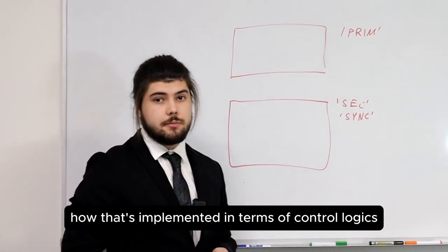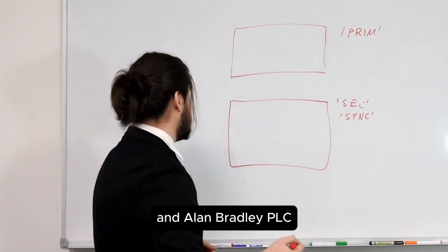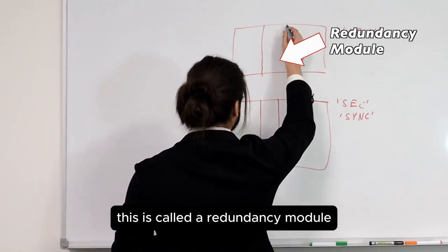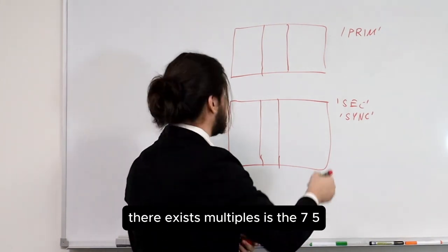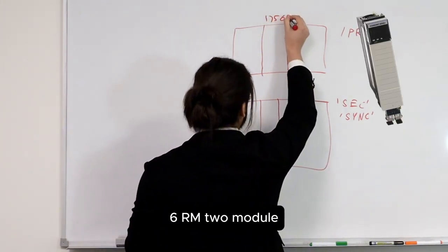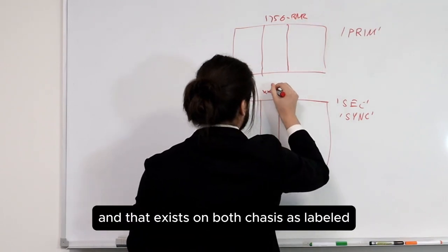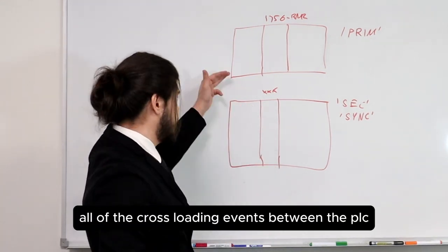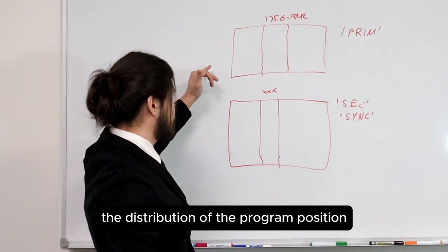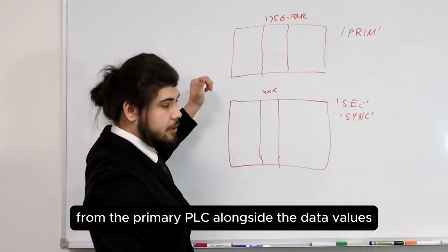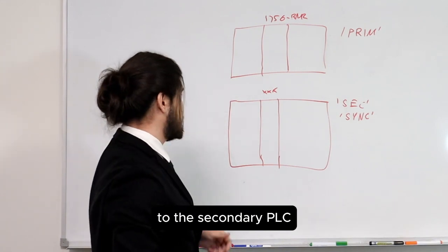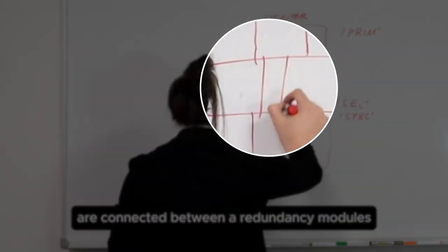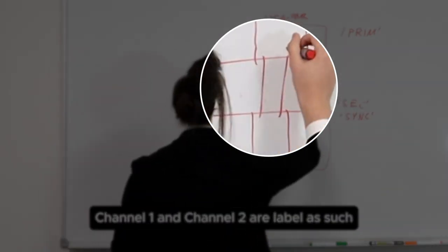How that's implemented in ControlLogix Allen Bradley PLCs is we have a specific module installed in both PLC racks called a redundancy module. The one we've been working on specifically is the 1756-RM2 module, and that exists on both chassis. This module controls all of the cross-loading events between the PLCs — an event which controls the distribution of the program position from the primary PLC alongside the data values at any given stage to the secondary PLC. For Allen Bradley PLCs, this is implemented through two fiber optic channels connected between the redundancy modules, labeled channel 1 and channel 2.